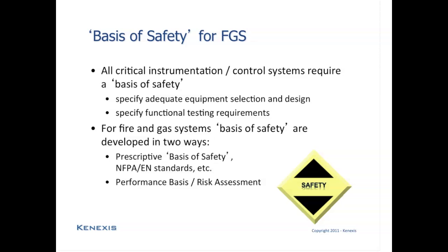Now that is the more traditional method, and there have been problems in using these prescriptive methods in that they don't allow for the optimal design for all situations, especially open air process plants and offshore oil and gas production facilities being a perfect example of where some of these prescriptive standards fall short of providing a good basis of safety. As a result, newer techniques have been used to try to create more optimal designs, and the basic description of the new methods are performance-based methods that use risk assessment to make the decisions as to where equipment is required and how often it would need to be tested.